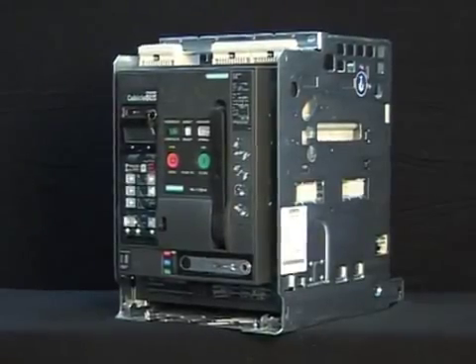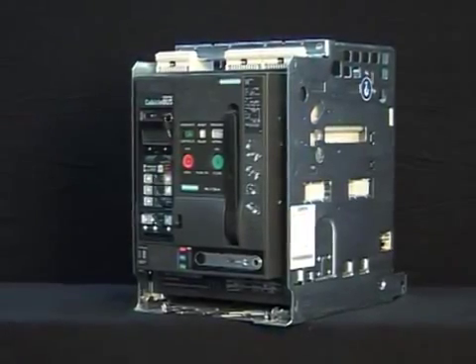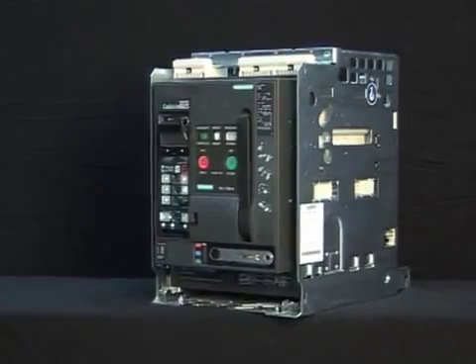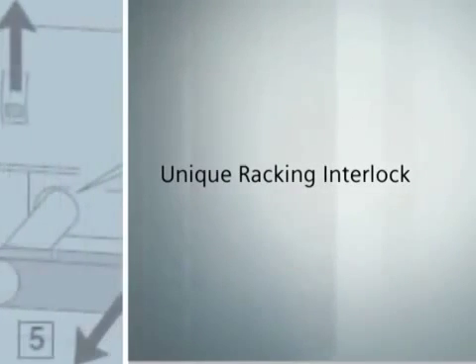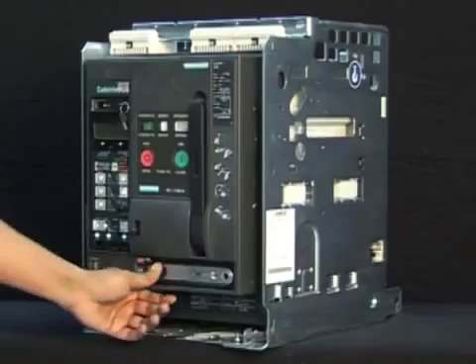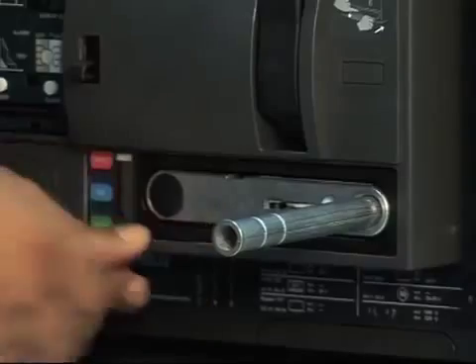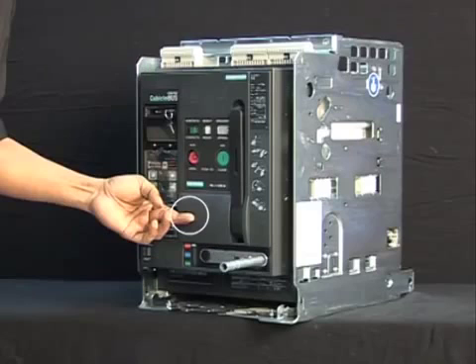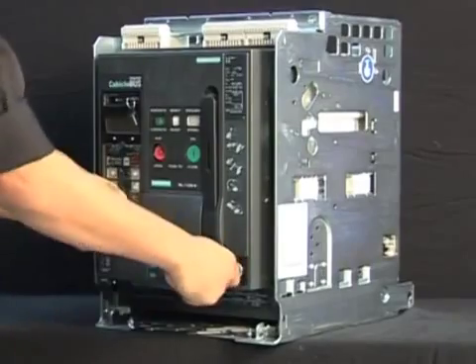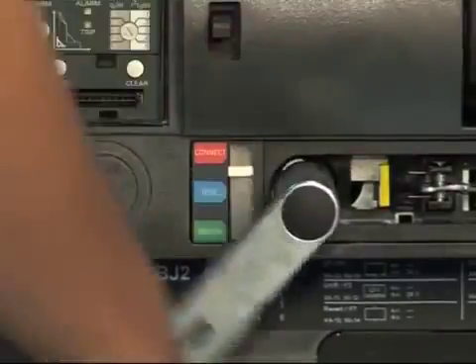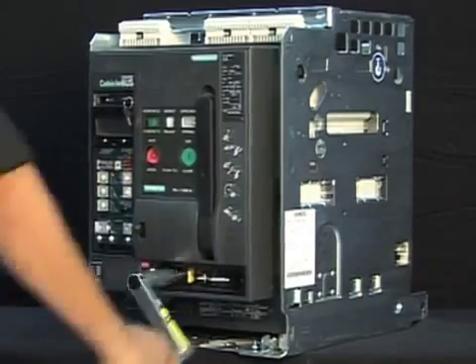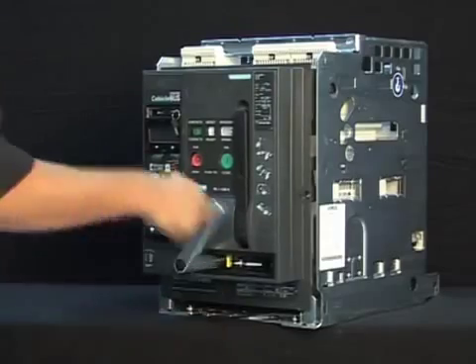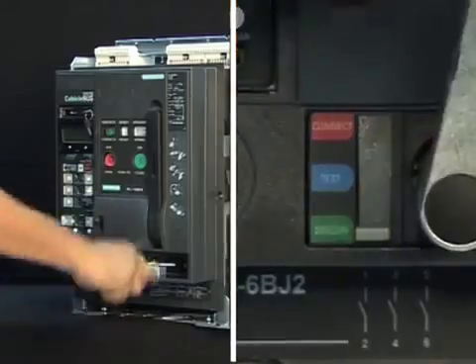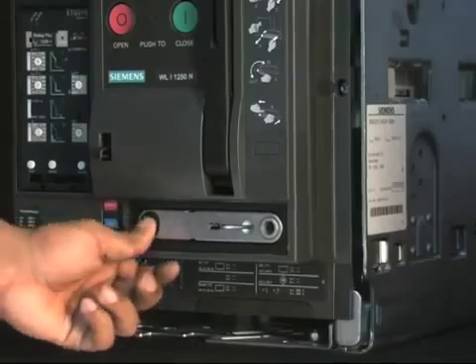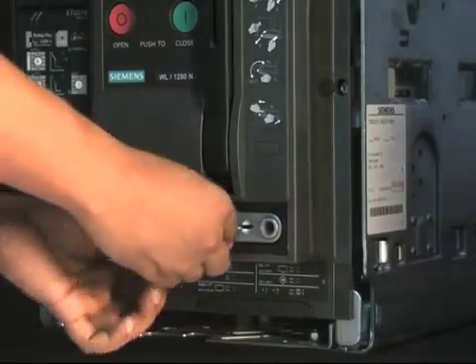Now, we shall demonstrate a very important safety function which is uniquely inbuilt in 3WL ACB to prevent any chance of accidental electrical shock to the operator. Unless you switch off the ACB, the racking handle does not come out of its slot. Even if you have not switched off the breaker, it automatically gets switched off when you lift and hold the control lever to extract the crank handle. Now, you can start the racking operation as the breaker comes out of the guide frame and keeps moving from connected to isolated position. The ACB is fitted with intelligent but simple padlocking facility which enables the user to padlock the ACB in any of the three positions.